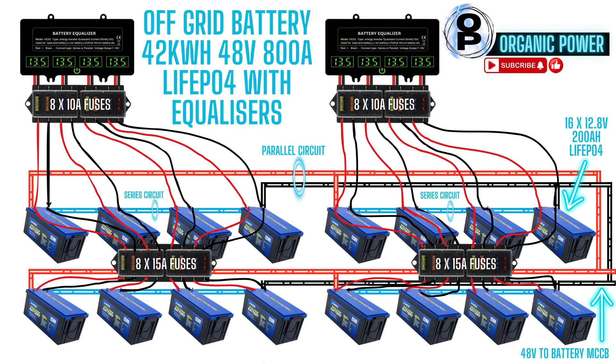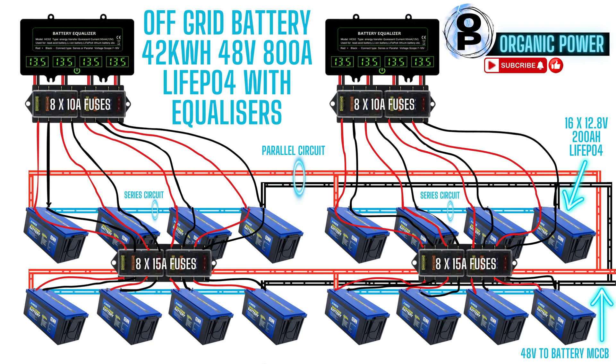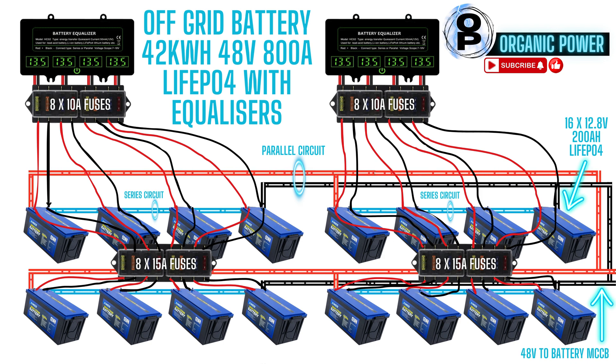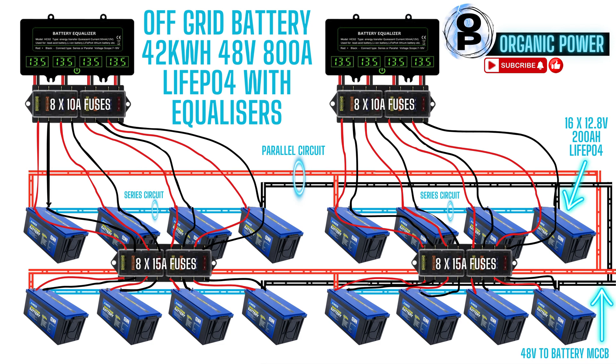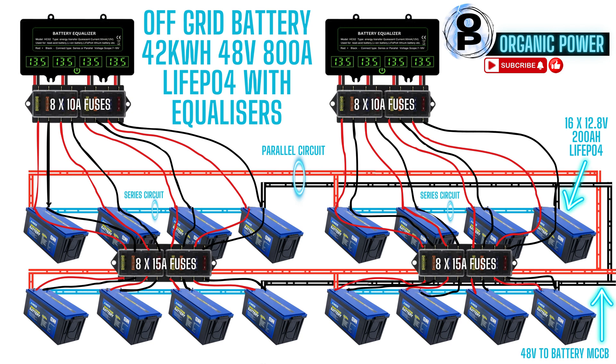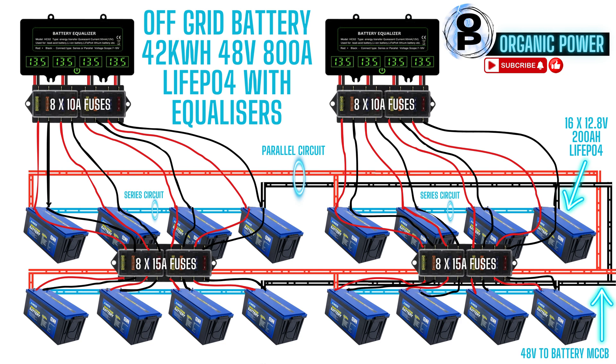Our off-grid battery consists of 16, 200 amp hour lithium phosphate batteries. We have four batteries in series and those four banks of batteries are then connected in parallel. That parallel circuit then feeds back to the 48 volt battery MCCB isolator.